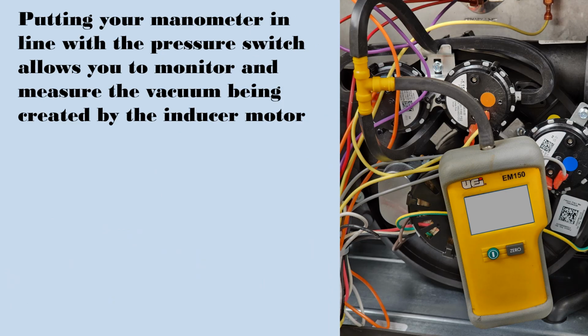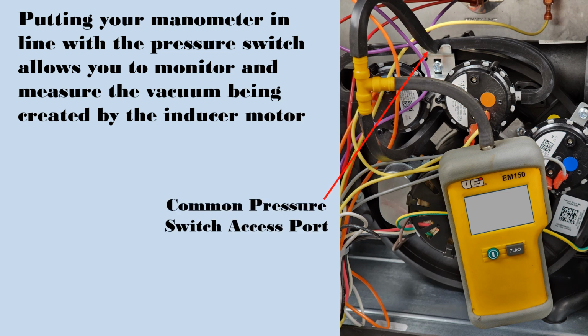Putting your manometer in line with the pressure switch allows you to monitor and measure the vacuum being created by the inducer motor. Common pressure switch access port there, because that access port's actually for both. It's common to both the low fire and the high fire. And draft inducer vacuum port in the back. And as we can see, we're teeing off, so we get the pressure reading there also.